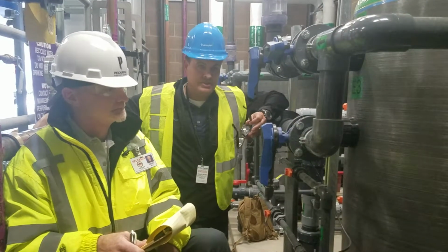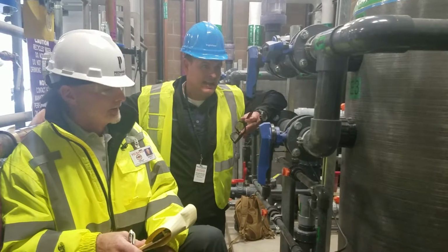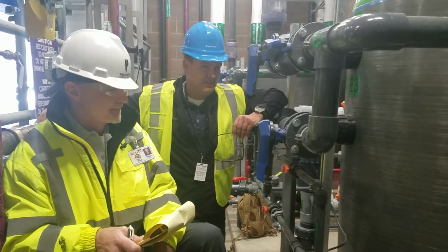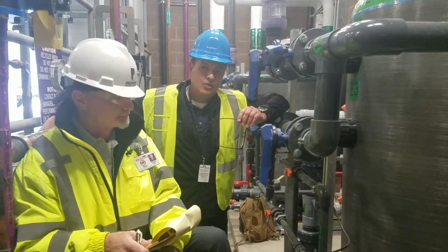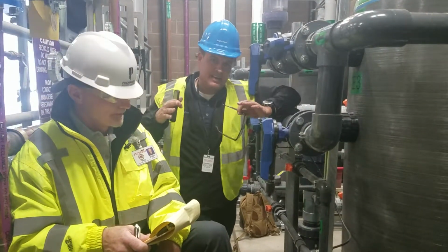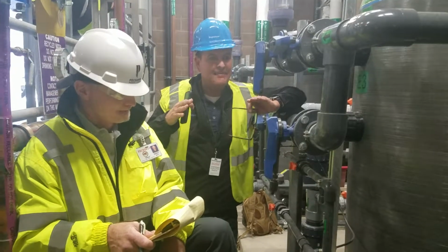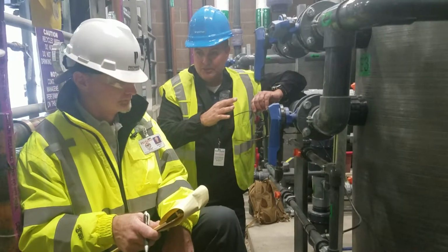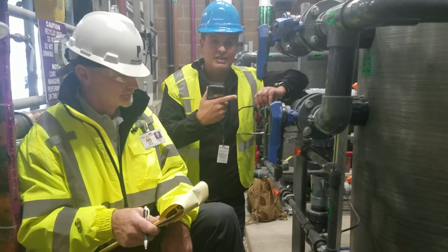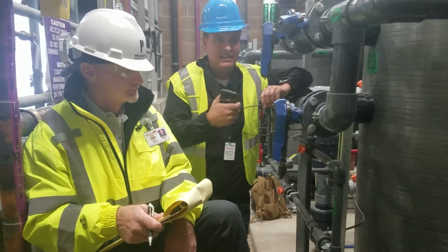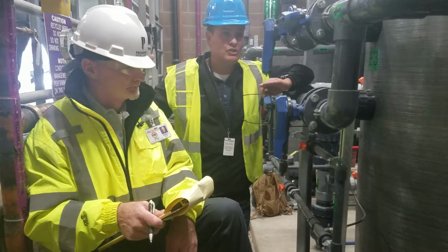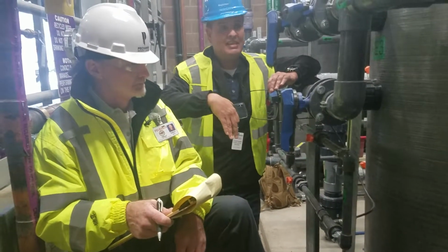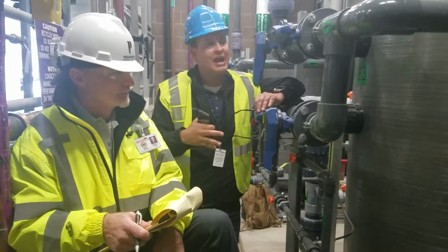Just so you guys know, we tested cyanuric acid in a controlled environment on control systems for about 2.5 years and gathered all the data. We know for a fact that cyanuric acid between a 10 and about a 17, somewhere in that range, has a pretty significant savings in chemicals, but it also allows the chlorine to kill single-cell bacteria in a timely fashion. Anything over 20 tends to be a waste. It's negligible. Everything after 20, it drops off drastically.